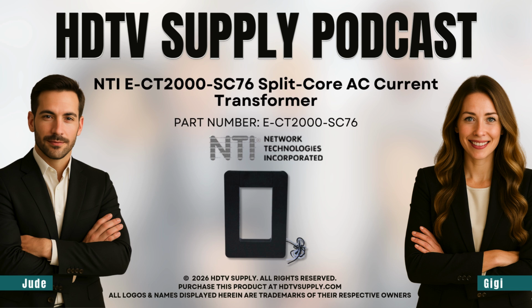We're looking at a single piece of hardware that's crucial for keeping huge industrial operations running: the NTI E-CT2000-SC76 split-core AC current transformer. Right away, that name tells you almost everything. The key number there is 2,000 amps. We are not talking about your server rack here—this is for monitoring massive electrical systems. That 2,000A capacity sets the stage for the entire discussion.